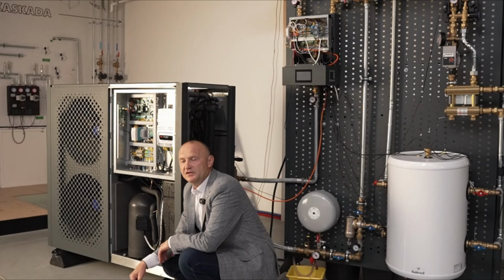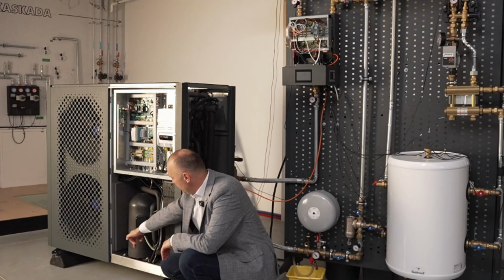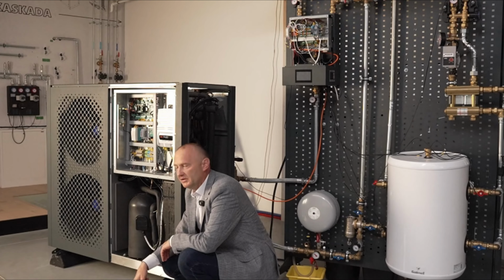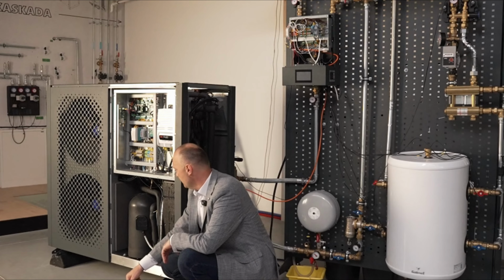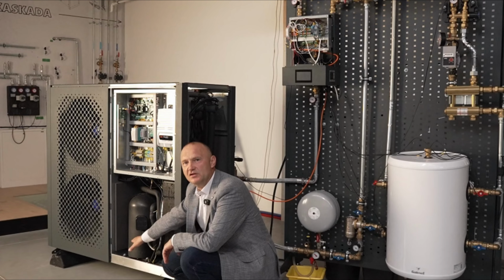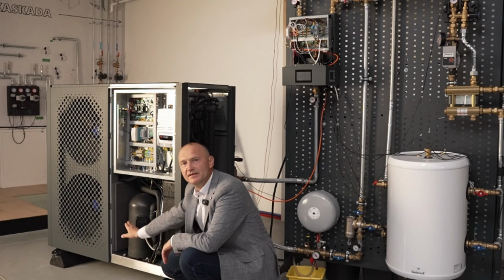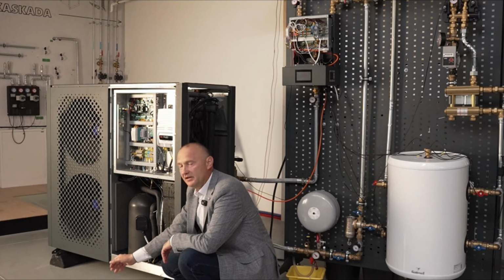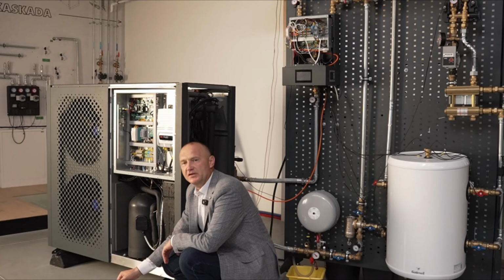This is a much better solution than in most compressors on the market, which have centrifugal lubrication or mechanical pump lubrication, meaning a pump whose output is dependent on the compressor's RPM. In this specific case, the lubrication is independent of the compressor's RPM. It doesn't matter if we operate at 900 RPM or at 7,000 RPM. Lubrication is just as effective because above the oil, there's roughly always a similar consistent pressure. This high pressure equally effectively pushes the oil into the lubrication channels, lubricating the entire compressor.